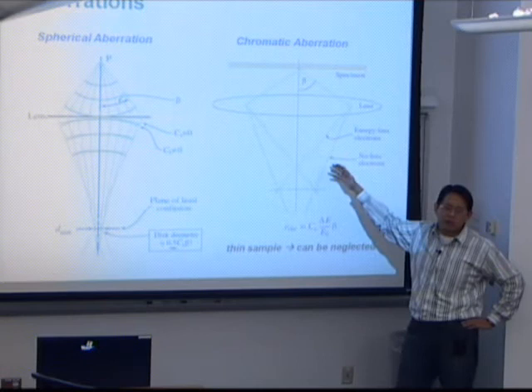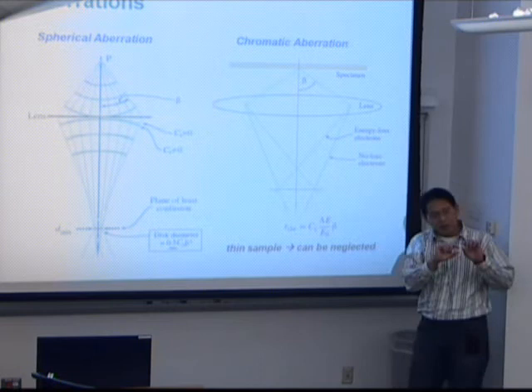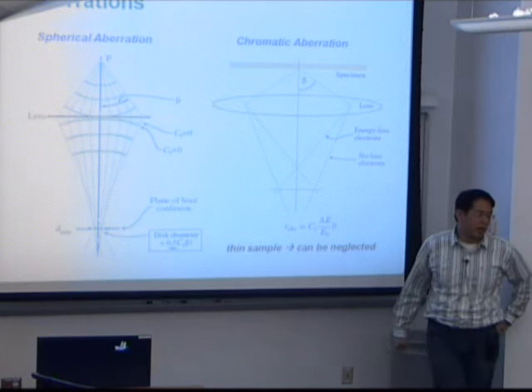There is also chromatic aberration: if you have different wavelengths of light, or in this case different energies of electrons, you get different refraction from the lenses. However, because we are talking about very thin samples — about 100 nanometers — in TEM this is not a major effect. The major effect reducing resolution is spherical aberration.